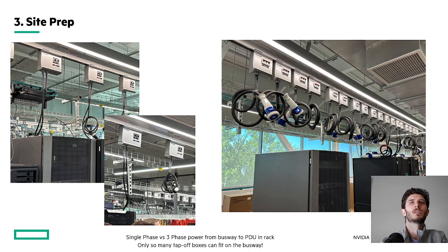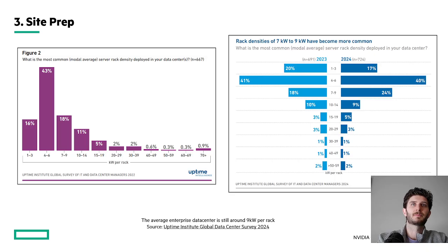If a single tap-off box is feeding a single PDU, and that PDU only consumes up to 17.2 kVA, about 17 kilowatts, to power some of the larger racks we have, which are 40 to 80 kilowatts, we actually need multiple drops to multiple PDUs in the environment to consume this. Even existing modern busways cannot fit enough tap-off boxes to run the power available, even if theoretically you could drive that amount of power to the busway.